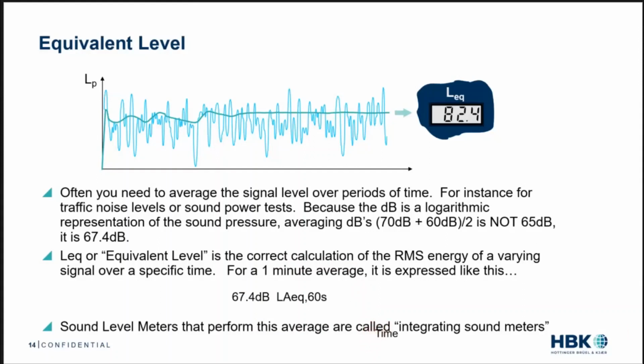Note that we no longer need to specify the RMS exponential weighting, fast or slow. The LEQ is a linear average. Every moment of the signal is considered equally in the calculation. If the time of the measurement is not specified in the measurement requirements, it is easy to look at the LEQ value as it updates to see where it does not seem to change significantly with increasing time. Some sound level meters use a parameter called standard deviation for the LEQ that helps you gain an understanding of the variation relative to the measurement time. Sound level meters with LEQ capability are called integrating sound level meters.